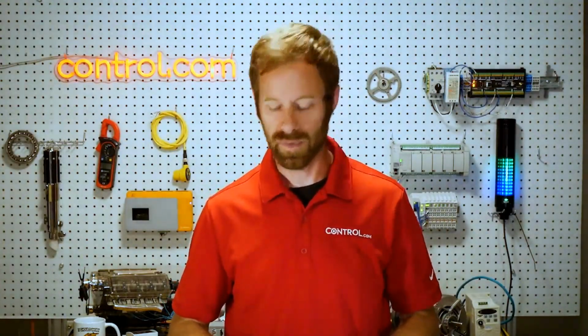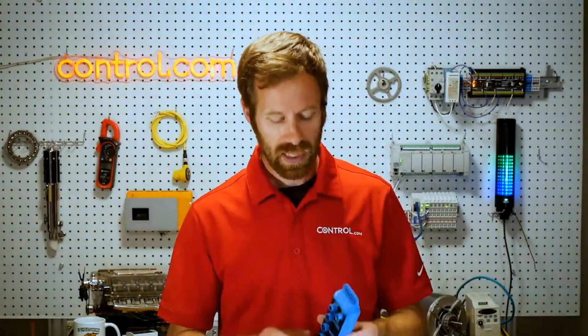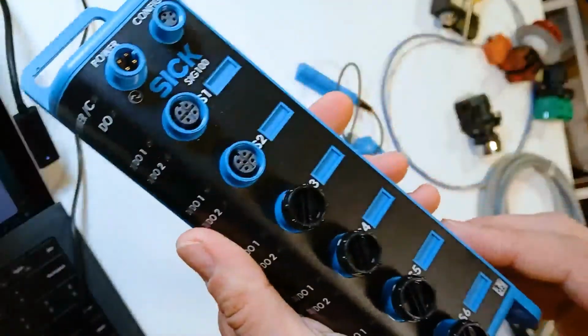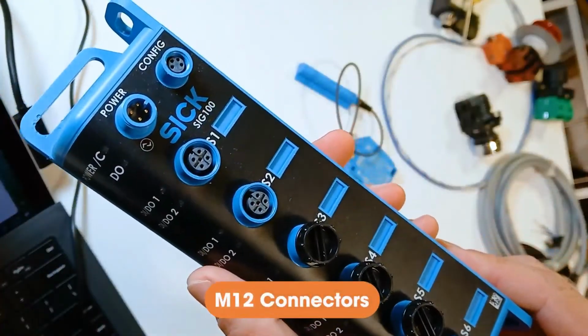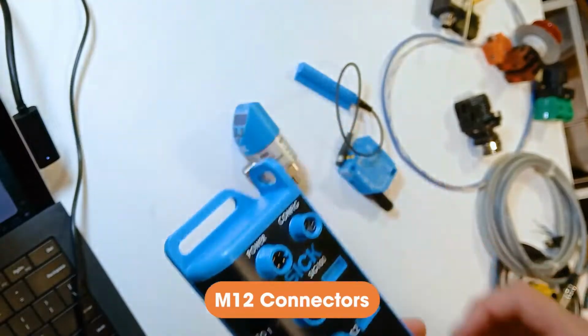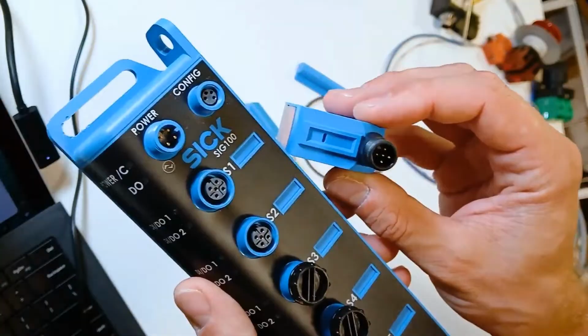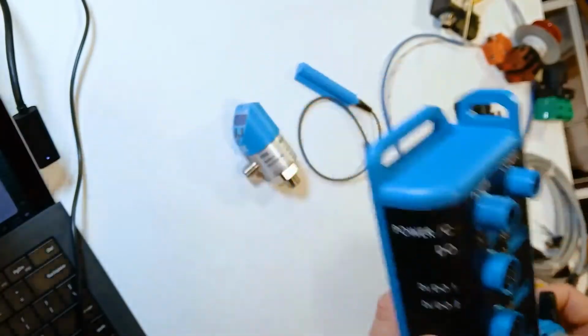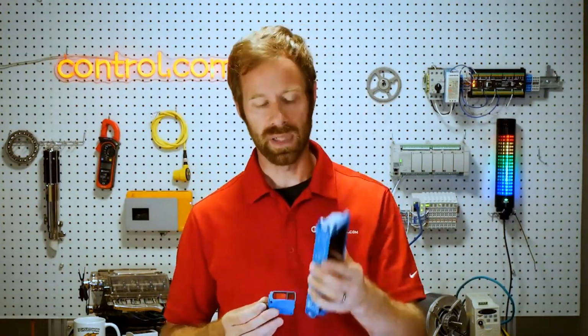Interestingly, this light behind me is also an I/O link device, and we can choose the colors, the speed that it's changing, all kinds of information from that. Although our discussion today is primarily focused on sensors. Each one of these connections is an M12, and that M12 is a 5-pin standard connector, and we see on the other end, the sensors have exactly the same kind of connection. So that means that we can connect this with a standard M12 cable to be able to connect our I/O link devices to the I/O link master.